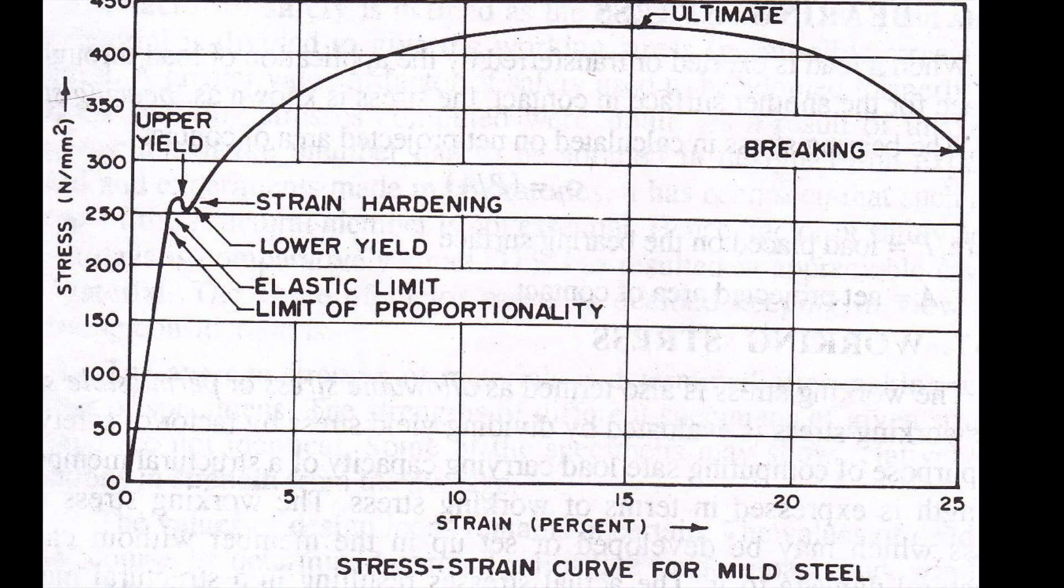On successful completion of the test, you'll see a graph like this on the machine's display. The first linear section is the elastic region, followed by a yield, and finally the curvy section is the plastic region and fracture. For a full explanation of this, watch our stress-strain curve video tutorial, which is linked above.